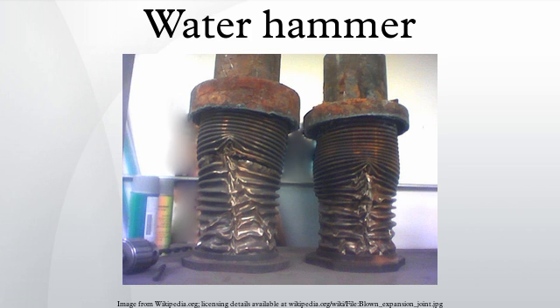Shorter branch pipe lengths. Shorter lengths of straight pipe, that is, add elbows, expansion loops. Water hammer is related to the speed of sound in the fluid, and elbows reduce the influences of pressure waves. Arranging the larger piping in loops that supply shorter, smaller run-out pipe branches. With looped piping, lower velocity flows from both sides of a loop can serve a branch.